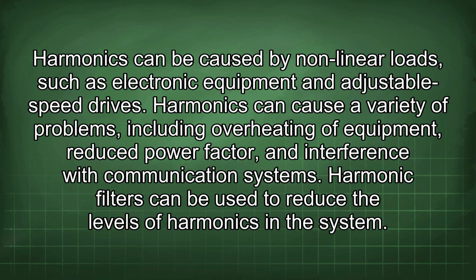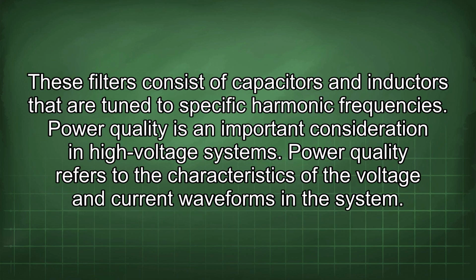Harmonic filters can be used to reduce the levels of harmonics in the system. These filters consist of capacitors and inductors that are tuned to specific harmonic frequencies. Power quality is an important consideration in high voltage systems. Power quality refers to the characteristics of the voltage and current waveforms in the system.